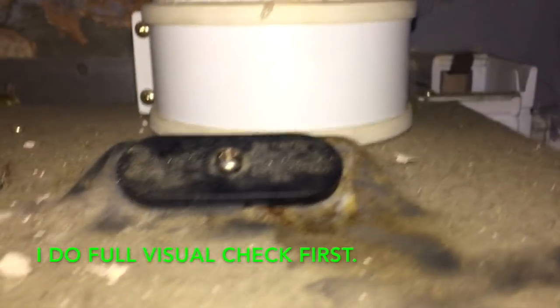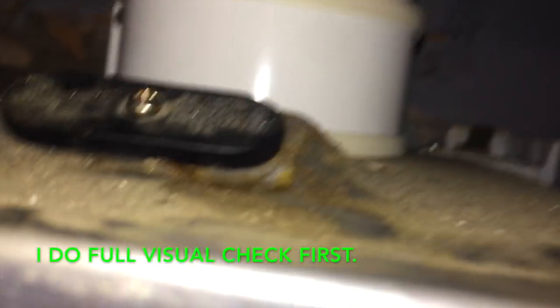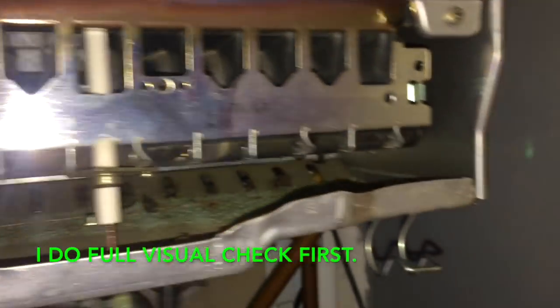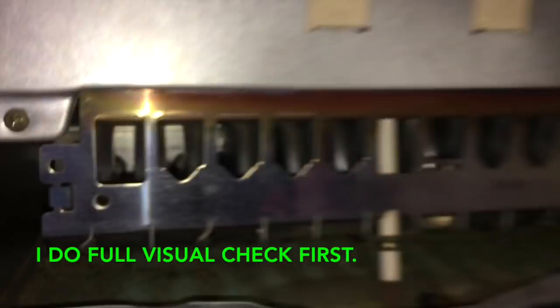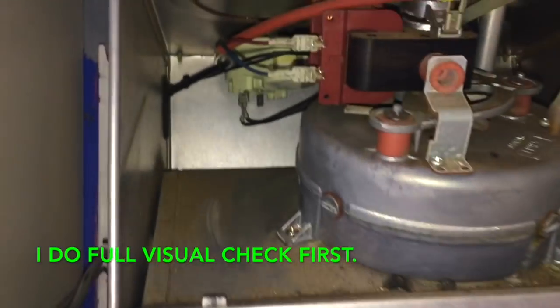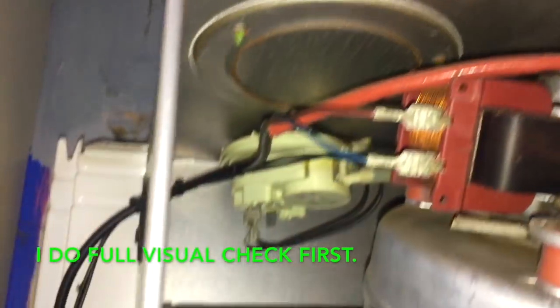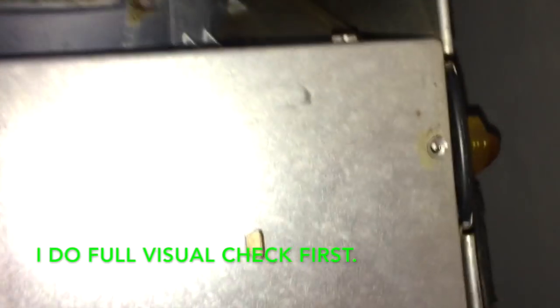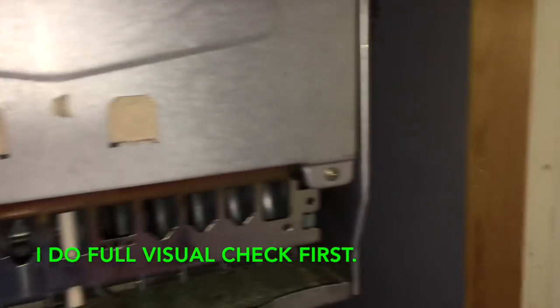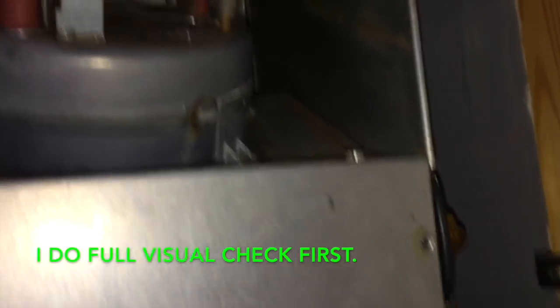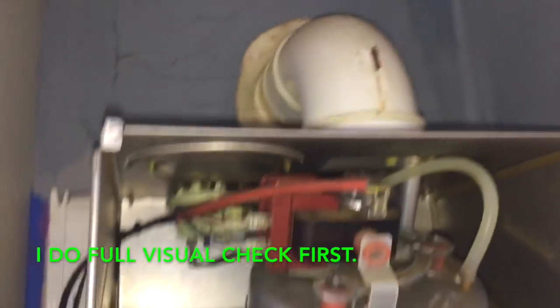It's a bit crusty, but there's nothing wrong with that, it's solid. It's all good. Look at that, okay. Seems to be okay, right. In here, we're going to take that front insulation panel off. Air pressure switch, fan, nothing else in there really. Electrode, air pressure switch, fan, burner, main heat exchanger. So I'm going to whip this cover off, undo the 2 screws at the bottom, we're missing the 2 further up. Have a look in there, do a visual and then get it back together and see what's what.